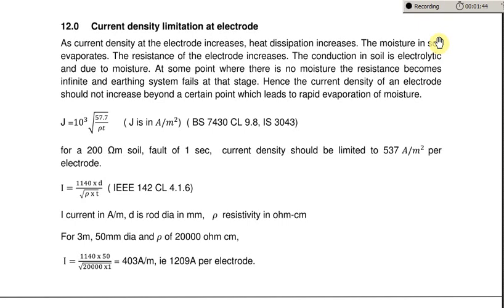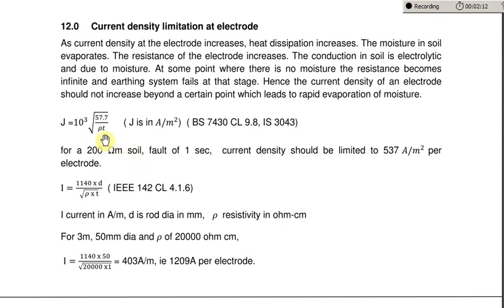Similarly, IS 3043 also gives a formula for this current density. You can see this formula where Rho is the resistivity of the soil in ohm-meter, T is the duration of the fault in seconds. We can take T as one second, and J gives the current density in amps per meter square.